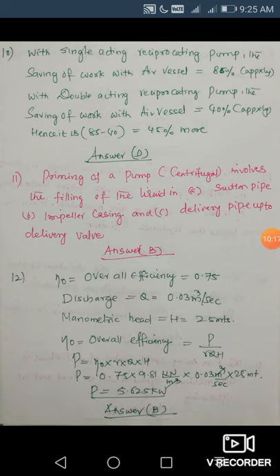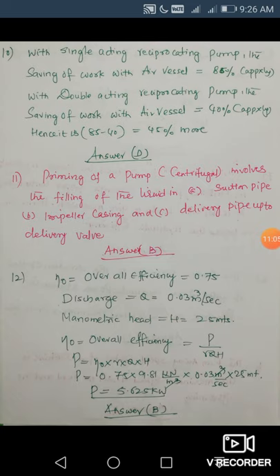Next question on priming of a pump: sometimes a pump is unable to pump liquid because of low available head. To remedy this, you fill the suction pipe, impeller casing, and also the delivery pipe up to the delivery valve with water, so that the proper head is available and the pump can operate. In centrifugal pumps, priming involves filling the liquid in the suction pipe, impeller casing, and delivery pipe up to the delivery valve. Select answer B.